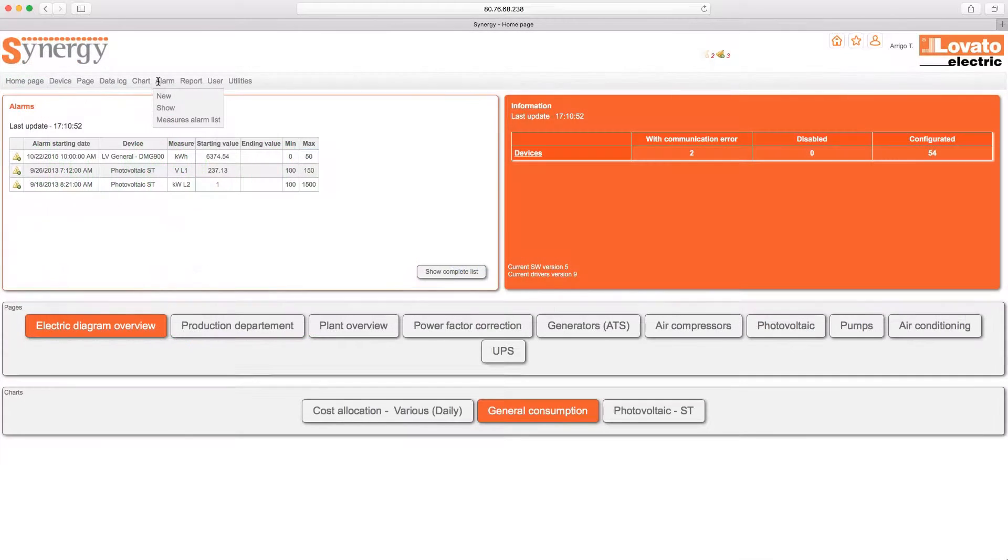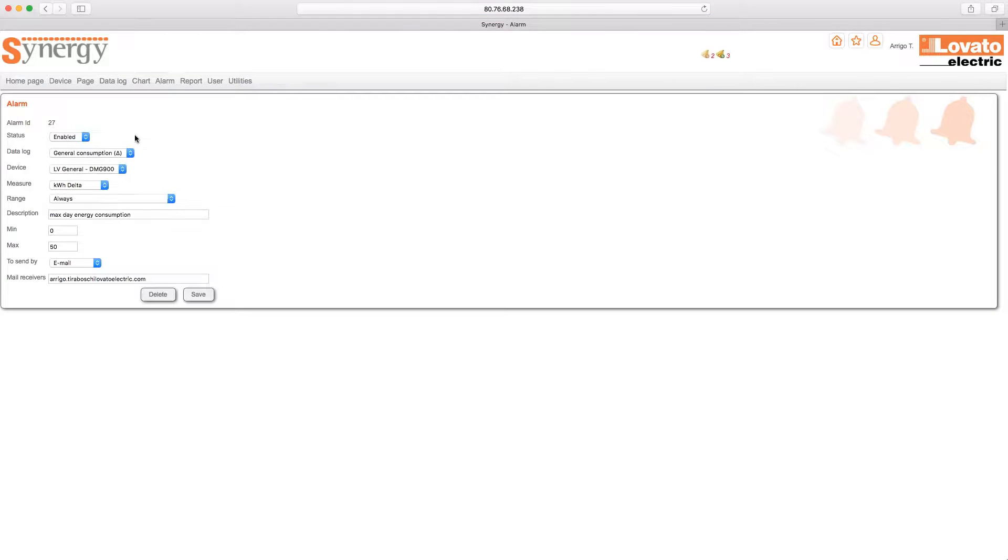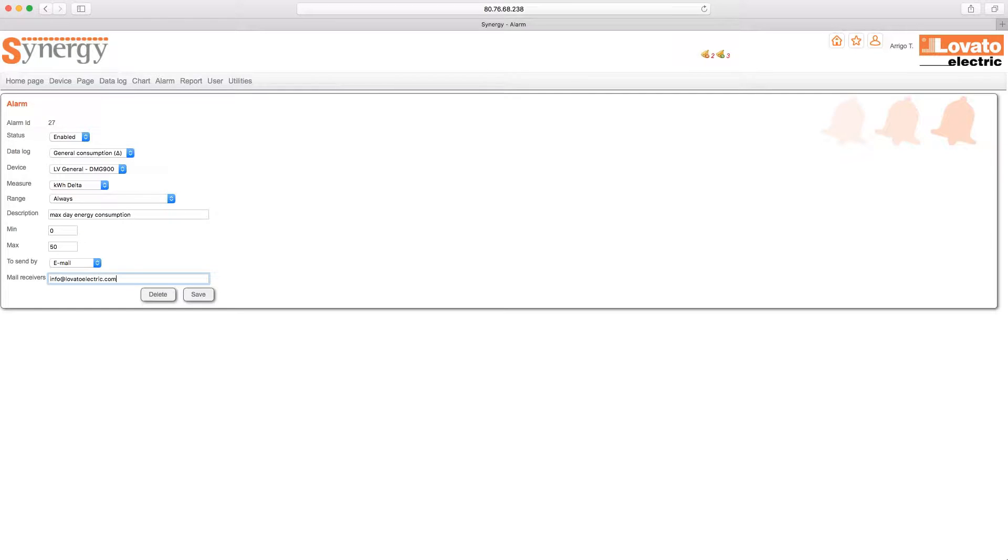Finally, the data logger can also be used to create alarms, setting thresholds that activate them. When the threshold is exceeded, in either direction, a bell will appear to warn you of the current alarm. You can then associate each alarm to one or more email addresses for immediate and active monitoring.